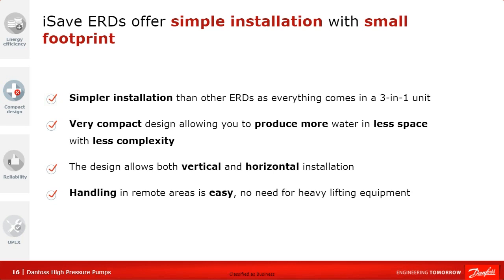The iSave is called a three-in-one because it combines the pressure exchanger, a positive displacement vane pump used as a booster pump, and a flow meter function — because it's a positive displacement pump, if you know the RPMs of the iSave you also know the flow on the high-pressure side. It is very compact in design, allowing more water production in less space with less complexity, and it can be placed in both vertical and horizontal positions.